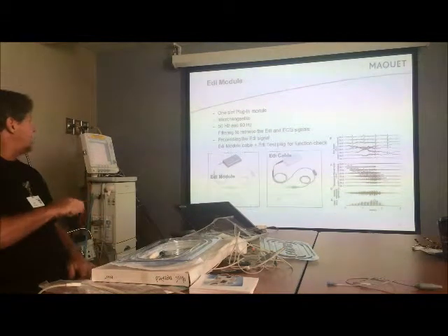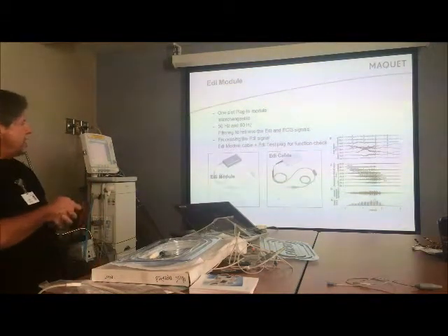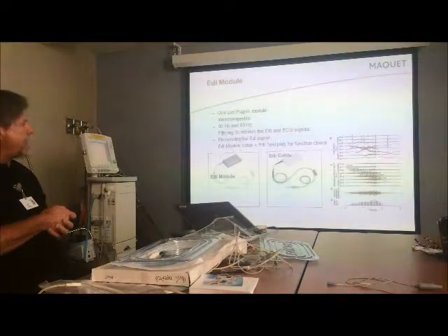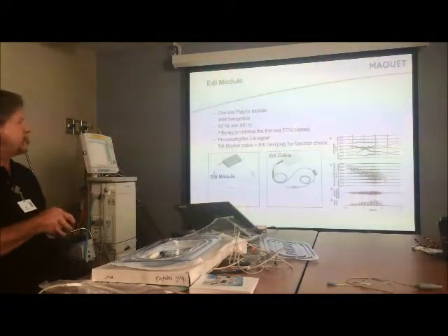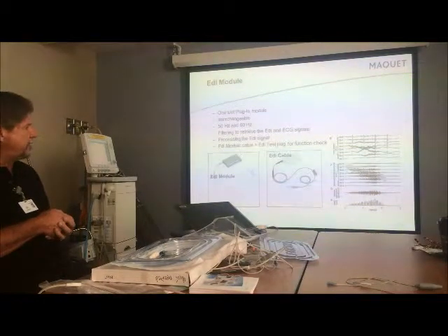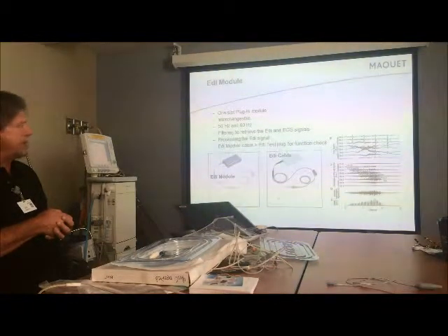You don't have to remember this, but keep in mind, as I said earlier, the electrodes pick up the electrical activity of the heart and the diaphragm, so we see the QRS signal here, but this is what the raw data looks like. You'll never see this on the ventilator, but this is what the ventilator sees internally.